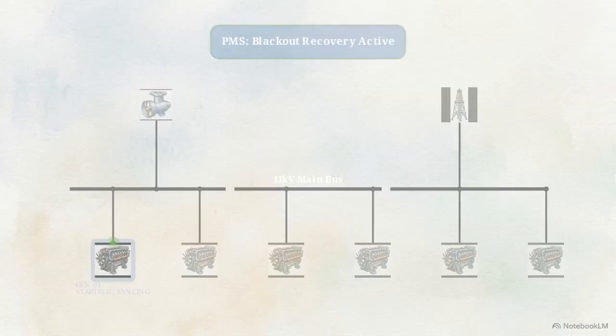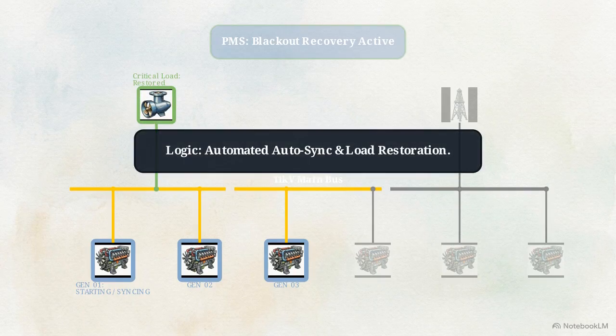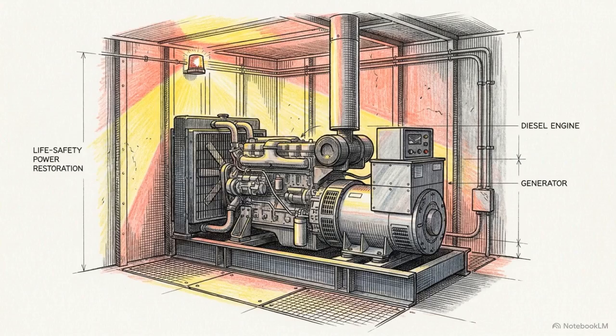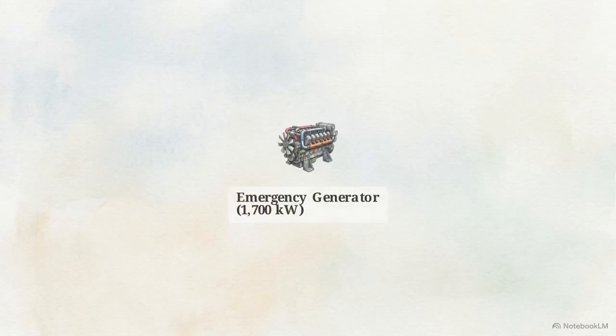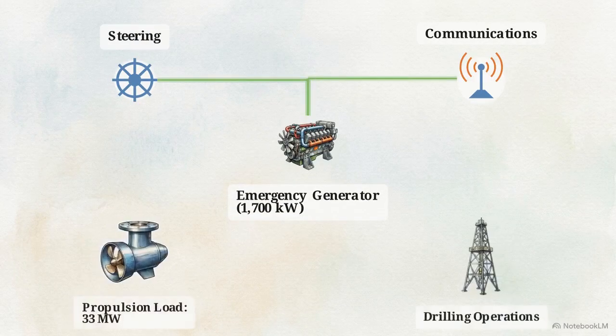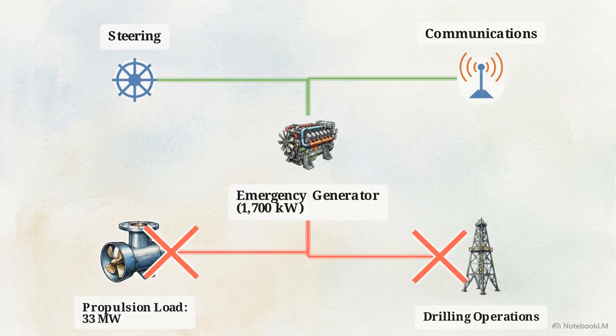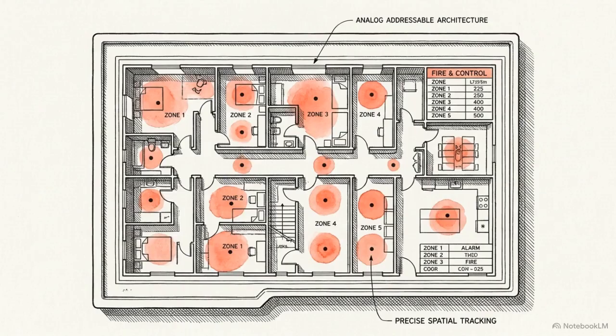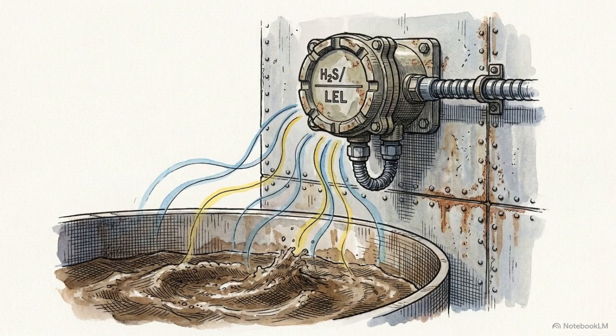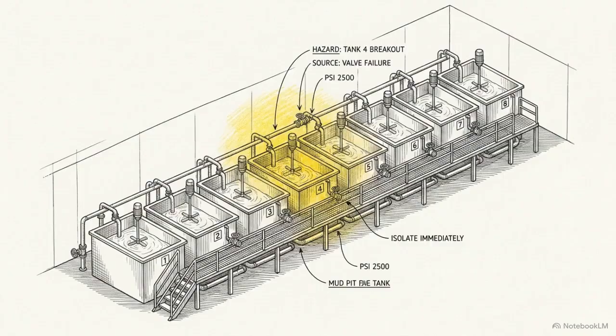The power management system handles this through fast blackout recovery logic, which automatically sequences the restart of generators and critical systems. An isolated 1700 kilowatt emergency generator starts immediately to restore power to life safety and navigation equipment. This emergency generator is sized only for critical loads, such as steering and communications. It cannot support drilling or propulsion. The fire and gas system utilizes an analog addressable architecture to remain functional and precise during emergencies. By placing LEL and H2S sensors directly at the mud pits and shaker rooms, the system can pinpoint the exact source of toxic gas breakout in real time.